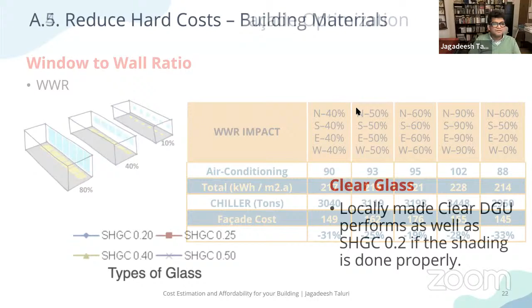In the same fashion, this is one aspect about local materials. One thing you'll hear is that if you want a low energy, low efficient building, the bylaws or guides may say you need a glass with shading and a solar heat gain coefficient (SHGC) of 0.2 or 0.25. These 0.2 to 0.25 glasses tend to be soft-coated glasses, which are imported and expensive.